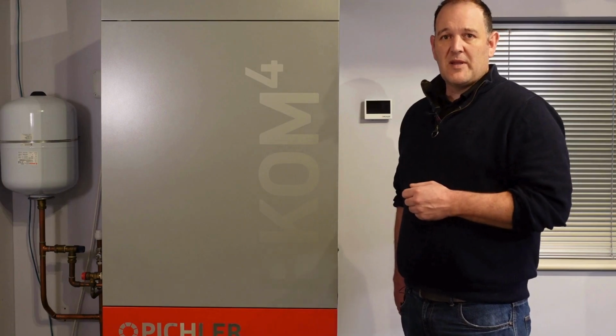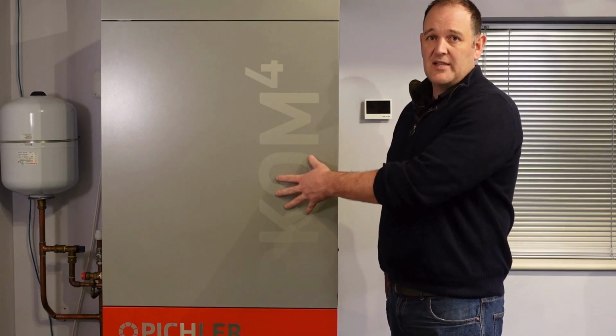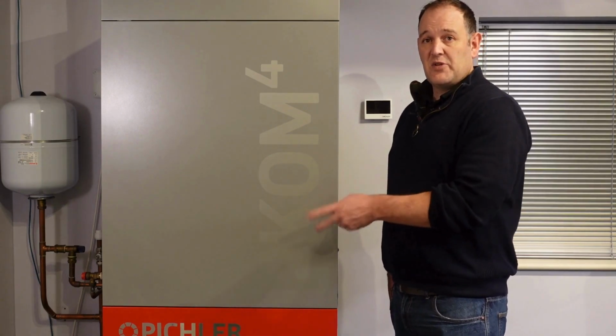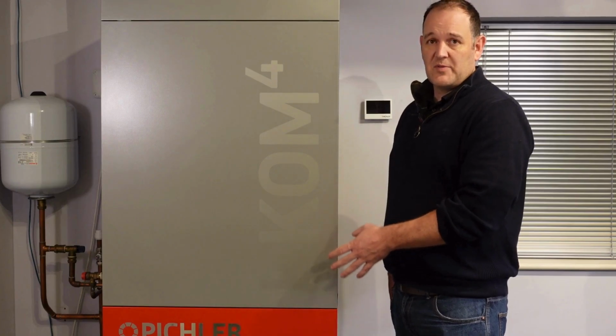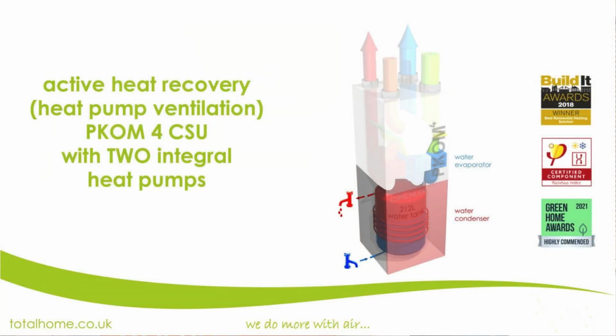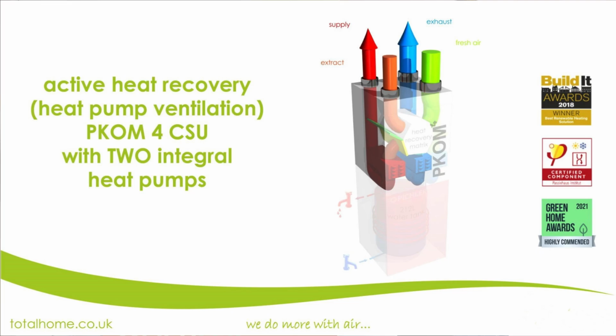Just so you know a little bit more about the PKOM, it is a ventilation system with a heat recovery heat exchanger inside. It also houses 2 heat pumps. One is responsible for the domestic hot water cylinder, the heating of that in the lower half, and the other is responsible for the space heating and cooling.